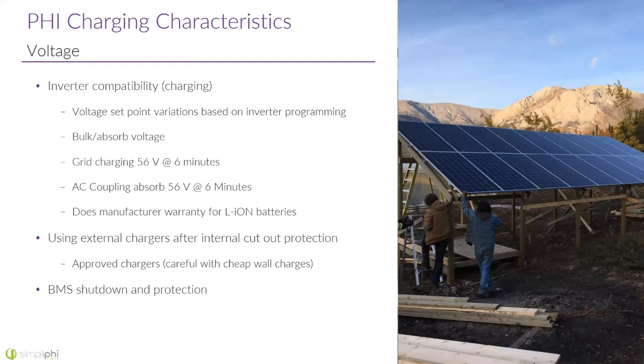Yeah, so with our batteries, again, we're using premium cells. We've got batteries that are going to last for, depending on how you program them, but if you program them to discharge down to a depth of about 20% state of charge, you're looking at about 10,000 cycles, which would be 27 years if you cycle once daily. And so even after 10,000 cycles, our batteries typically still have about 80 to 90% of the original capacity left in them. So there's not a huge difference in the amp hour capacity.